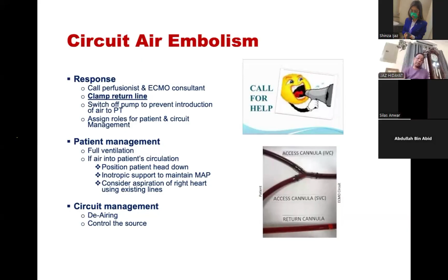50 cc, 50 cc. And once you are sure there is no air, keep the RPM at like 1000 RPM, inform the team that you are going back to full flow, slowly open the return line and achieve your full flow. So this is the management of air in the circuit: de-air properly and find the source of air. If you do not find the source of air, then air will come back again into the circuit.